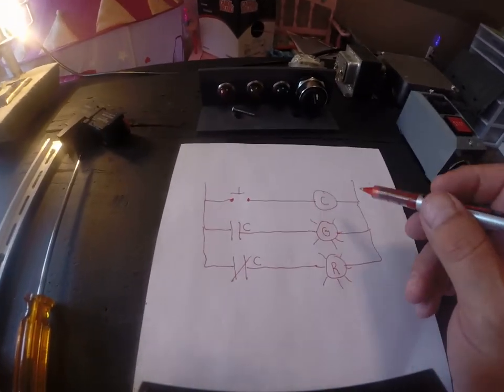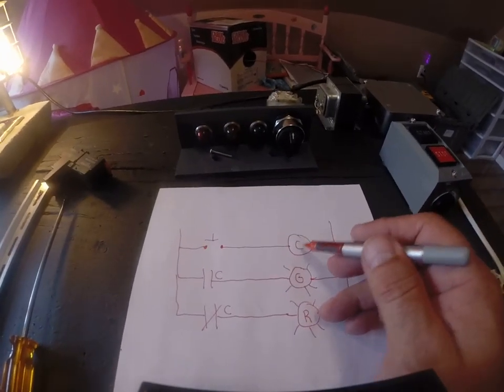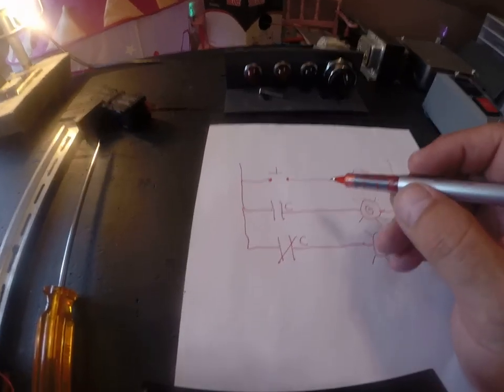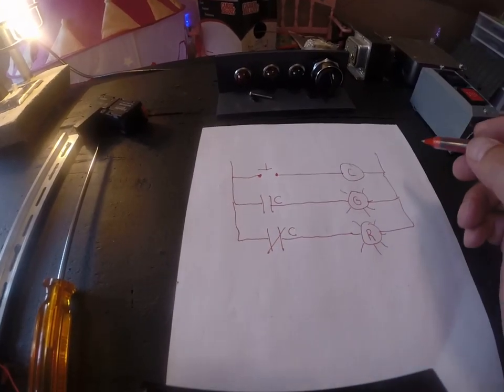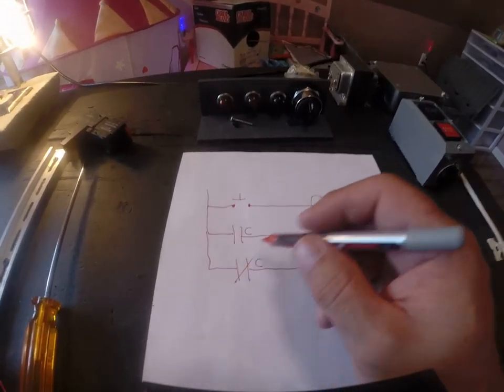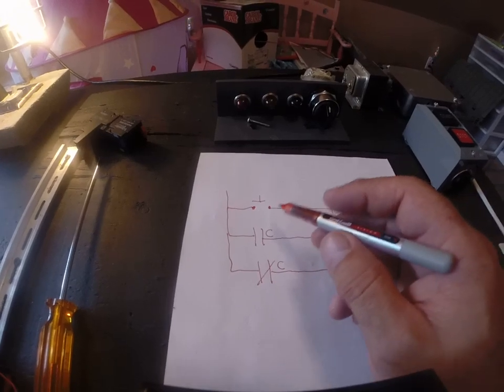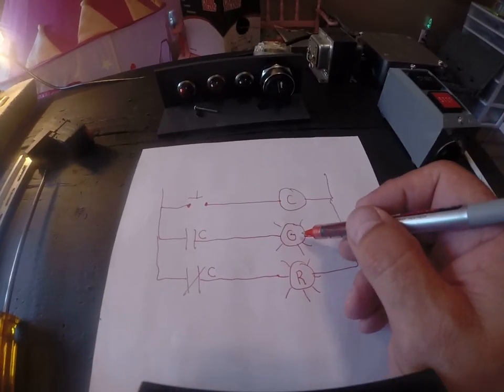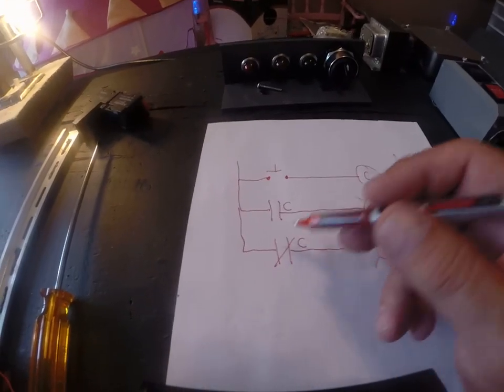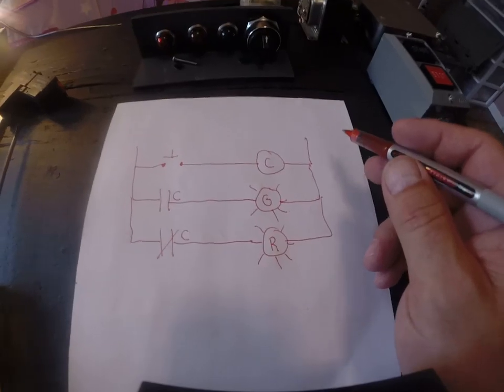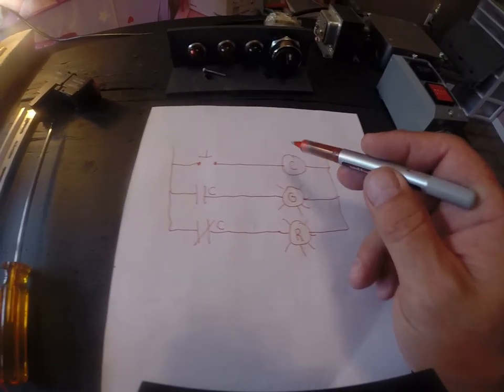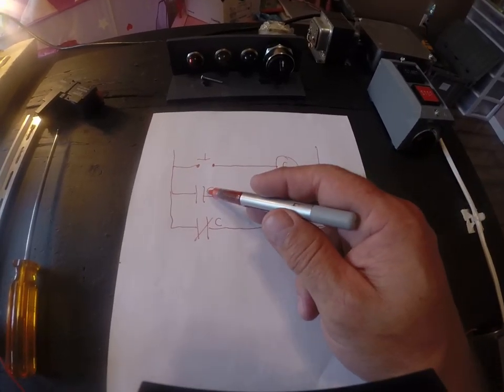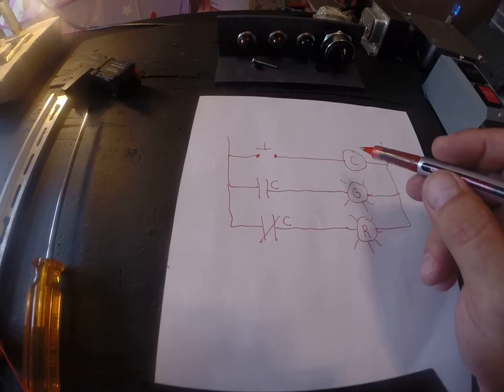So to simplify this if I press this start button and hold it, this becomes energized. And what's going to happen is this is going to close and this is going to open. This will close allowing the green light to come on. This will open taking away the red light. So this is very basic. But understand when I energize a relay, whatever contact positions they were in, they're going to change to their opposite state.